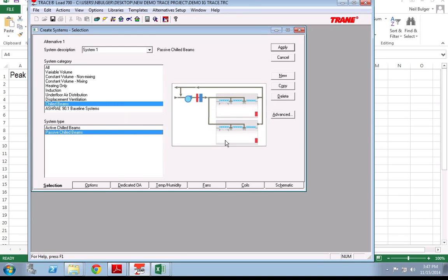So that's all fine and good, but why are we talking about this? Sometimes this all comes back to when you have a distributed cooling system, and we need to size each room for its cooling load, and then we also need to size the cooling coil at the roof level, which you size for ventilation air and then more air if needed for additional cooling.